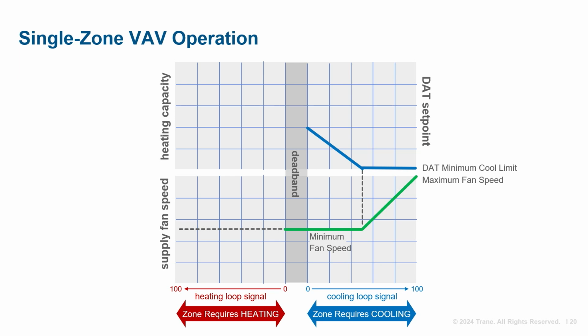fan speed changes. Now, some heat pump units may require a constant volume of supply airflow through the heat exchanger during heating, while others might be capable of modulating airflow while heating. This could be accomplished with staged heat pump operation. Here's an example with 2 stages of heat. When the zone temperature drops to its heating set point, the first stage of heat is activated, and the supply fan modulates to maintain zone temperature at its heating set point. When the second stage of heat is activated, the supply fan operates at full speed. Both a single-zone 2-speed fan system and single-zone VAV system might be applied in the same way.